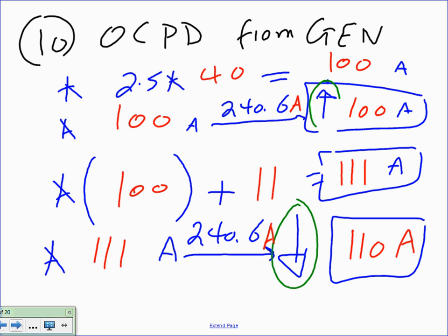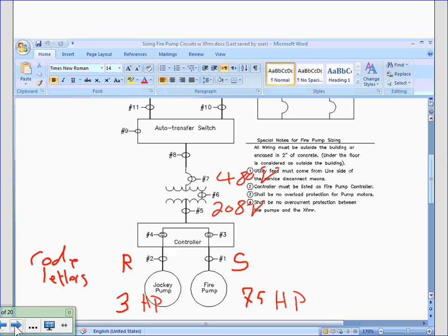So we have a 400 amp circuit breaker on the utility side and 110 on the generator side. That drives some people nuts. The code allows you to do that. And those of you who were in the presentation here, we said it's highly unlikely, guys, that you're going to have an emergency and your generator is also running at the same time. So we can handle 110 and overloading, and also locked rotor current on your pump. So if that happens, you're out of luck, basically. Okay, so this is the first example that we're going to do.